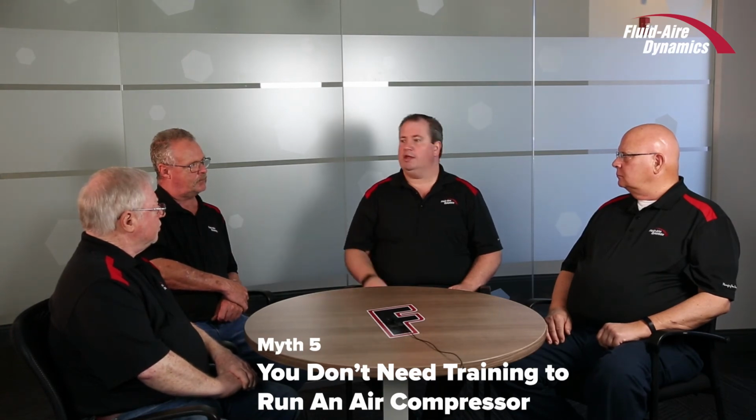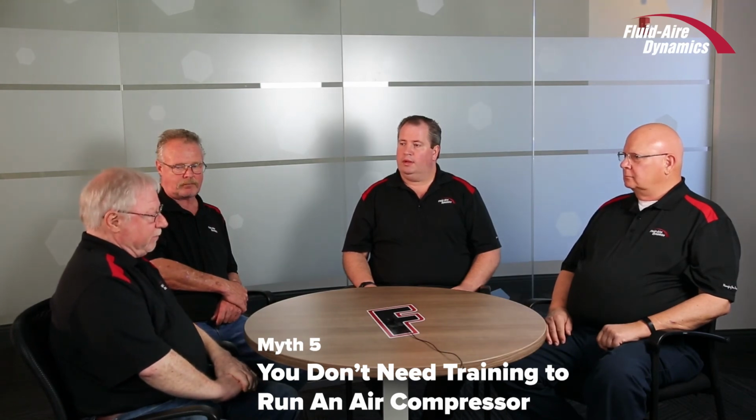So training, whether it's data logging or explaining to them that compressed air costs this much, that if you can hear it, it's at least 1 CFM that you should fix. The ROI is extremely quick. Maybe you can add to that. No, obviously anything you hear you fix. But we can go around with sonic leak detectors and find even the smallest leaks. They tend to add up, but if you can hear it, you can walk through your plant on a Saturday morning, turn your air compressor on, and take a listen to what is actually leaking.